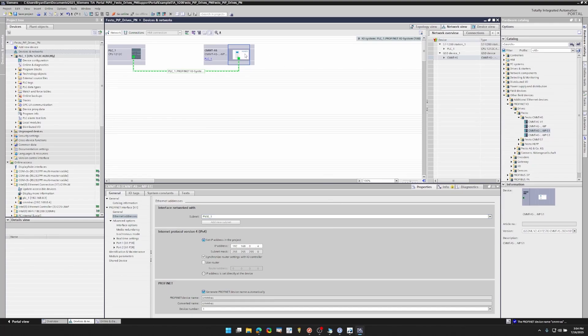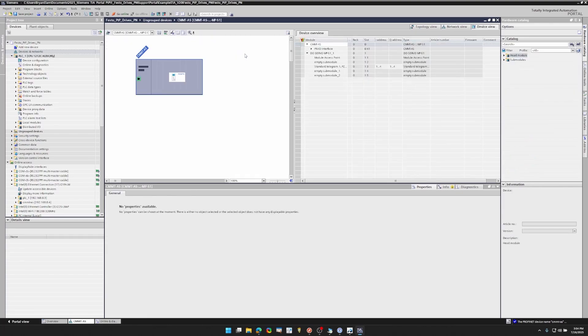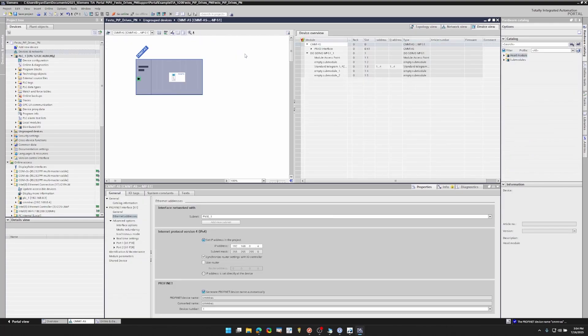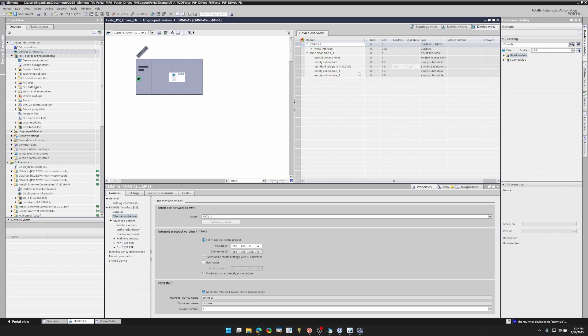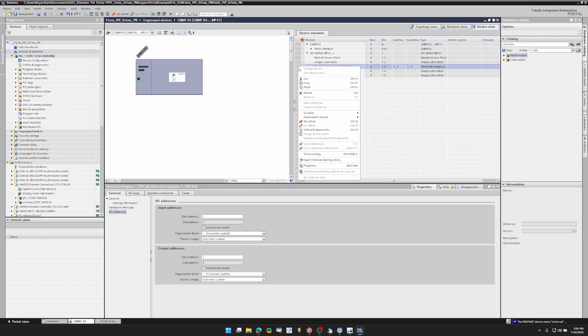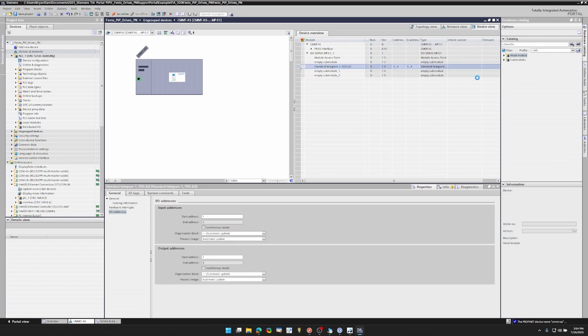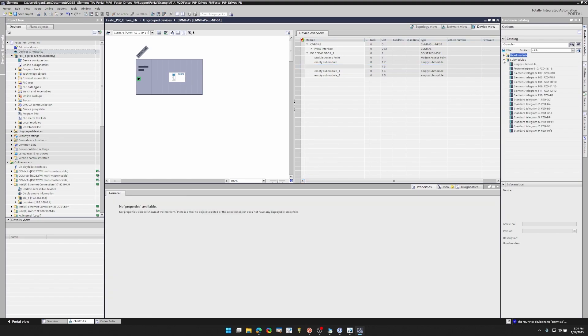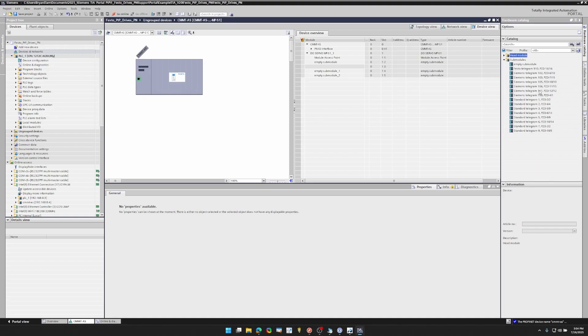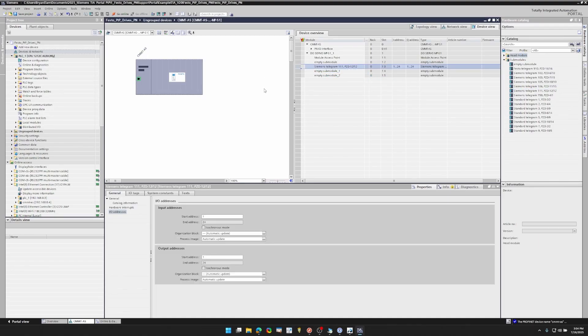Okay, now we want to set up our telegram for the servo drive. So right now you'll see that there's standard telegram 1 in this section, which is good for setting up speed or other simple parameters, but we need to delete that so we can use standard telegram 111. And there's a host of various telegrams that you can select from depending on what function blocks you're using. Like I said, standard telegram 111 is going to be good for us here for the point-to-point function block.